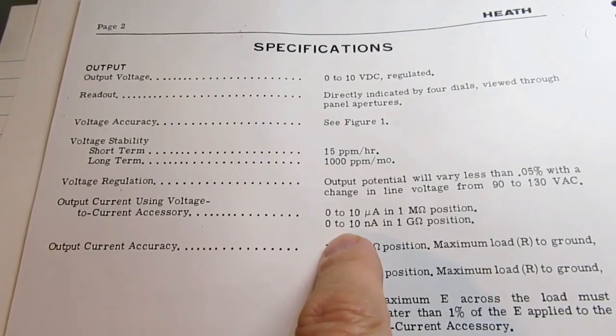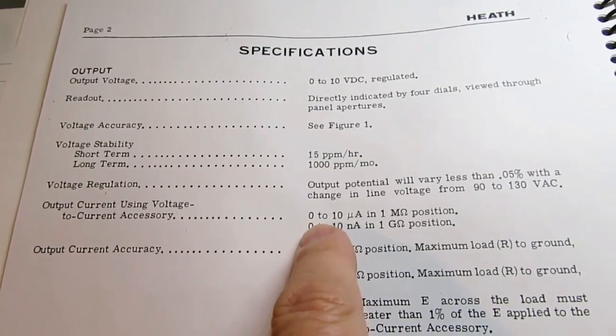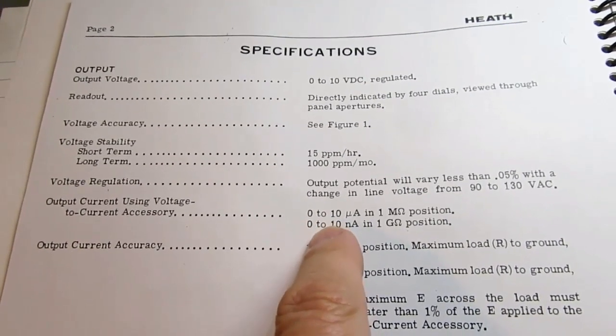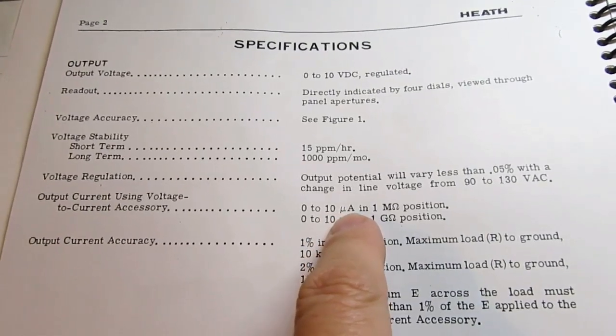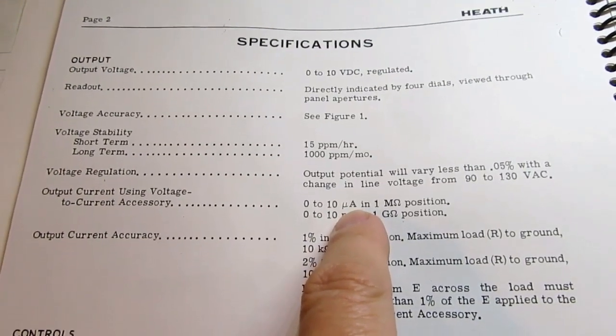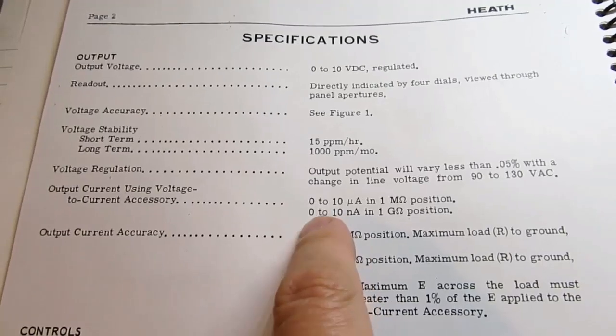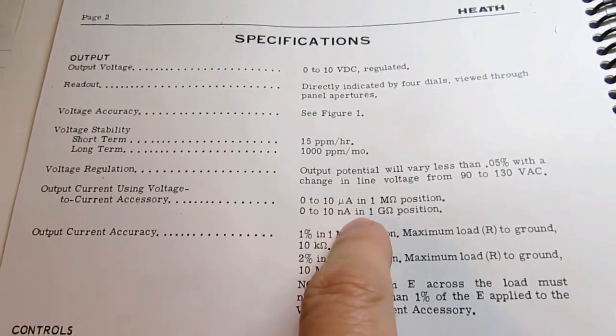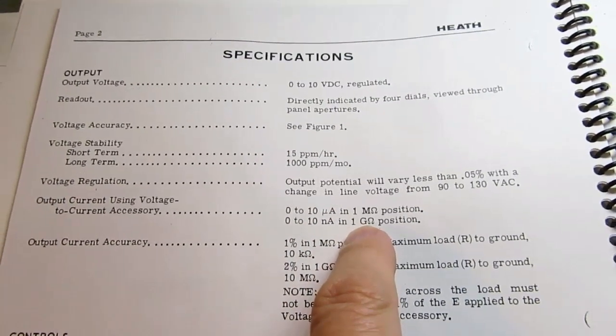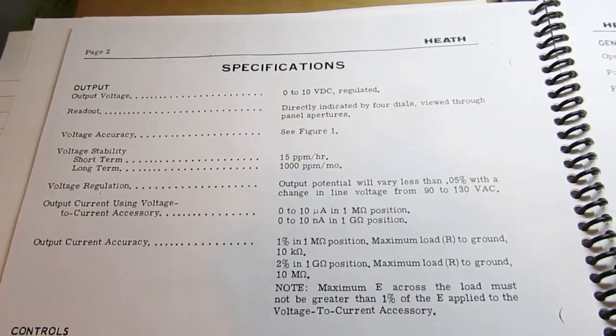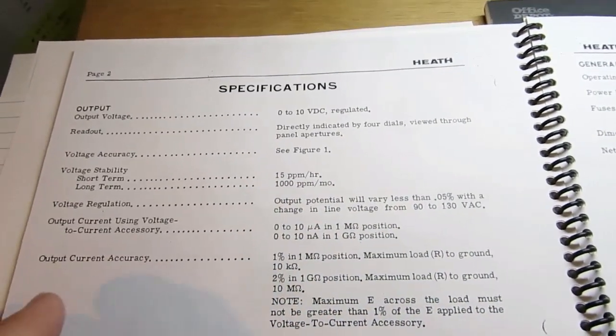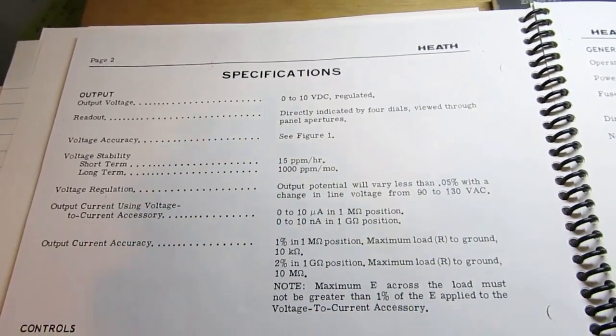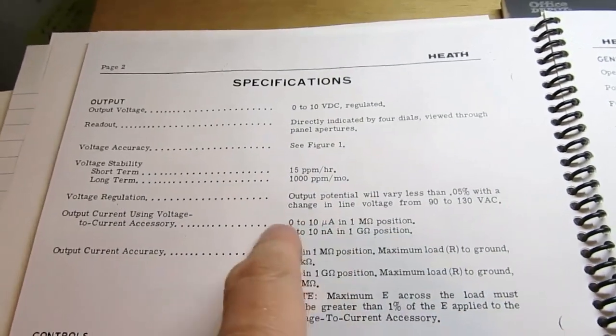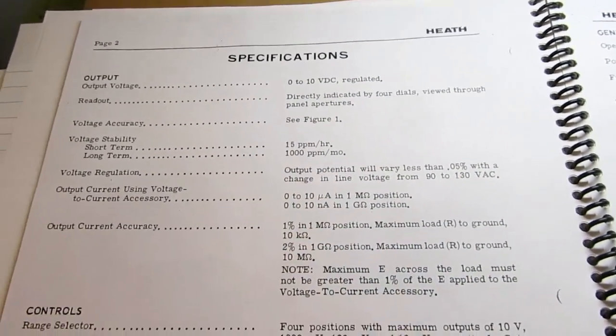With the voltage to current accessory, you can get up to 10 microamps in one position of the switch and 0 to 10 nanoamps in the other position of the switch. And that's based on setting the actual voltage reference in its 0 to 10 volt range and then using it with that accessory to get those currents.